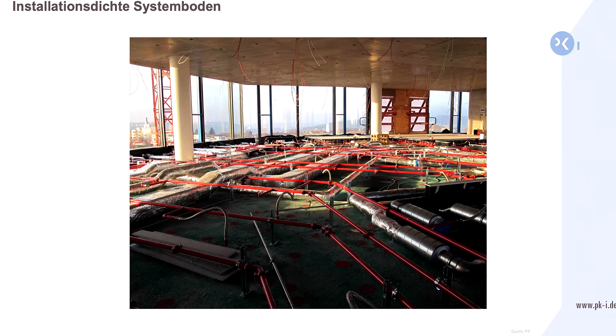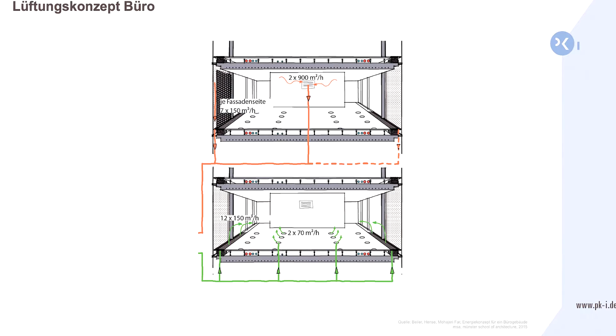Well, in the office itself, we have a specific innovation, the exhaust air facade. Intake air comes out of the floor centrally, also in the window areas at the facades. It is sucked off centrally at the elevator cores and at the sides of the facades in a switched fashion. This takes us to the exhaust air facade. Whenever the sun shines on one facade, a screen is activated, the screen moves down and shades very efficiently, but the screen is inside. Here you see it in the cut. The solar protection screen moves down, and with the lateral areas it seals off, and thus it forms an exhaust air duct.